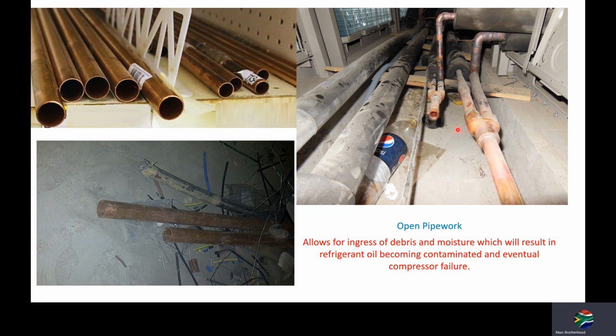Also, a lot of moisture going in. If you don't achieve proper vacuums, you will have your oil turning acidic and eating the insulation of your stator within the compressor, and you're going to end up with a short circuit. So it's very important. You have to close off all pipework on site. You can even get little bits of metal or plastic going in the pipework. It will ultimately be captured by the filter, but it is not an ideal environment. Very, very dangerous for the longevity of the system.